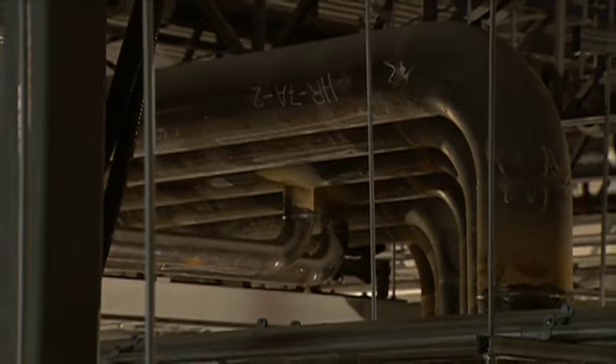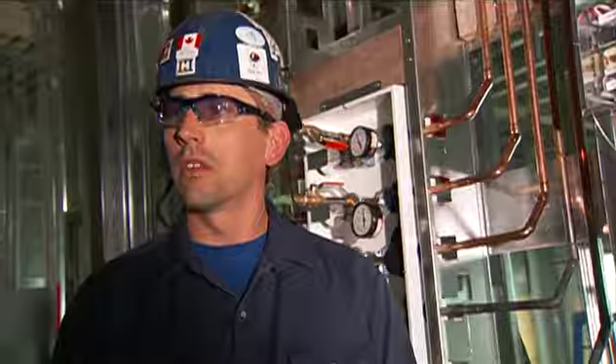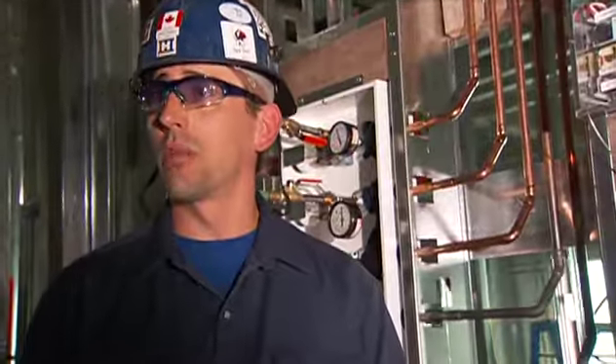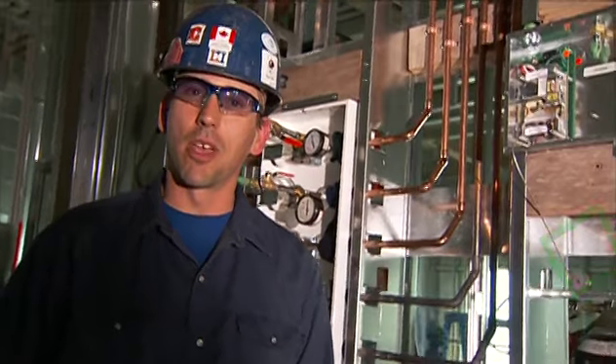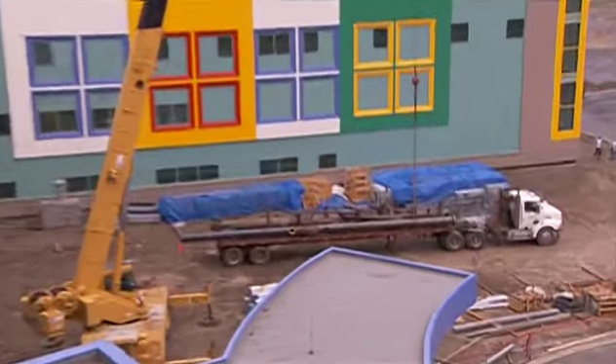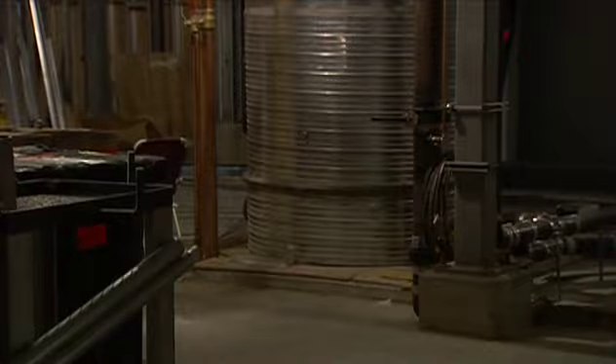Along with wires, we've also got a lot of mechanical piping. In total, there's 4 million pounds of pressurized pipe in this hospital. That's a lot of pipe. And it took 49 trucks to deliver 21 air handling units that together weigh over 1 million pounds. 48% of the cost of the facility is mechanical and electrical, and if you compared that to an office building, it's typically 18 to 20%. So it really is like no other building.